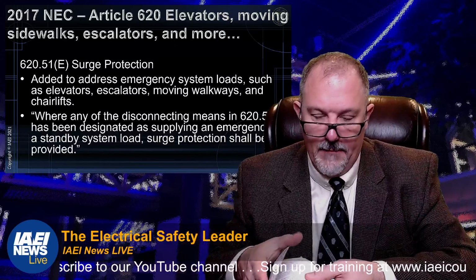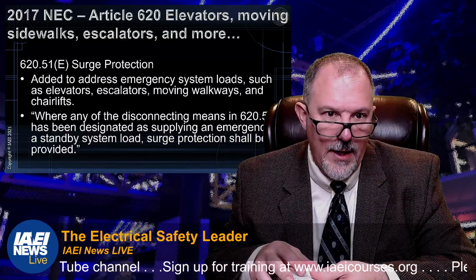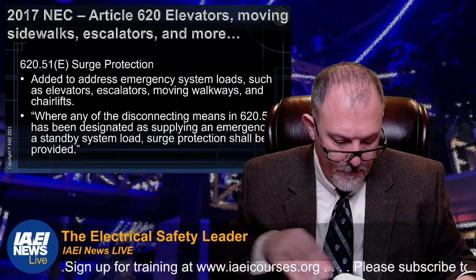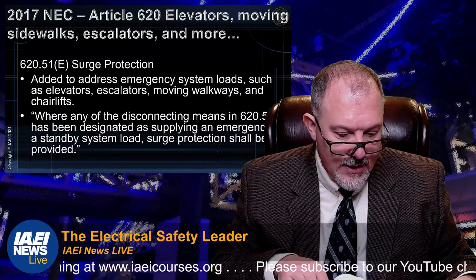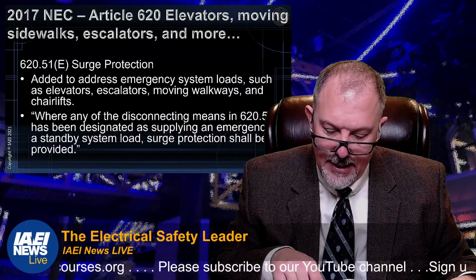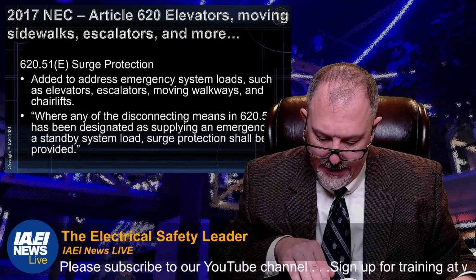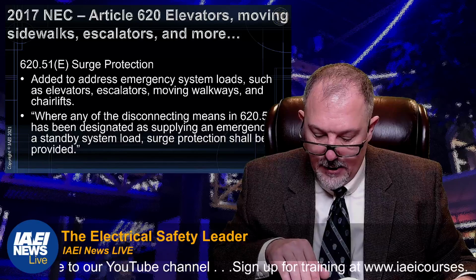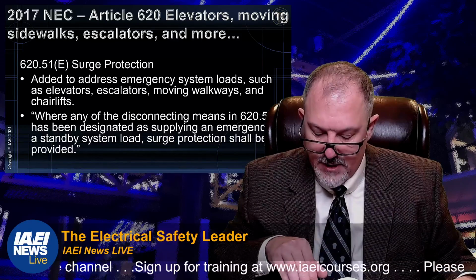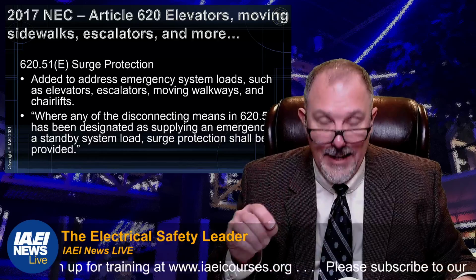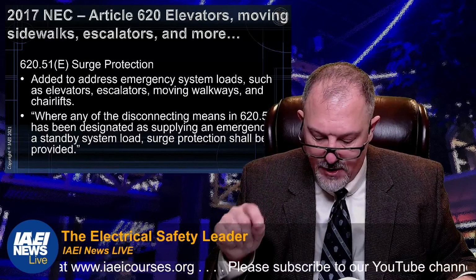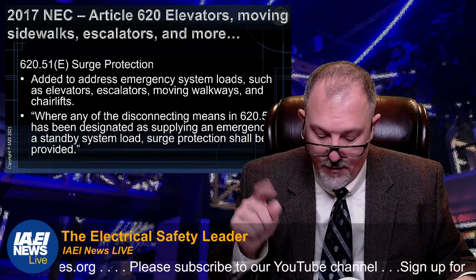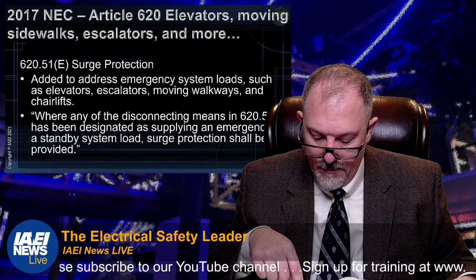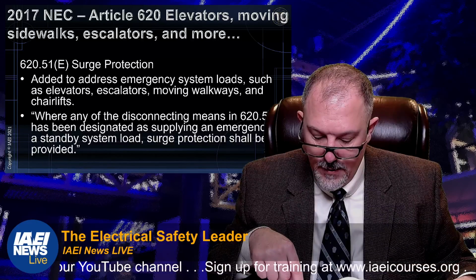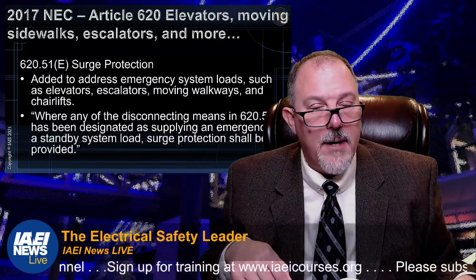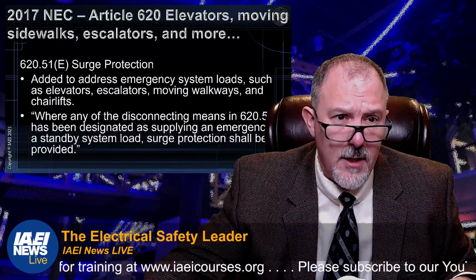620.51E. What happened in 620? That's your elevators, people movers. 620.51 ABC, D, identification and signs. E, not D, E. Okay, it was in the 2020 code. Where any of the disconnecting means in 620.51 has been designated as supplying an emergency system load, a legally required system load, or a critical operation power system load, listed surge protection shall be provided. So they added the legally required system load or a critical operation power system. They added those two references. Surge got a little love in the 2017.